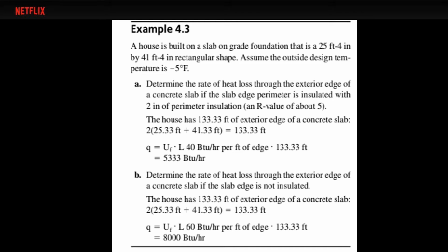So, next. Example 4.3, a house is built on a slab on grade foundation that is 25 feet 4 inches by 41 feet 4 inches in rectangular shape. Assume the outside design temperature is -5 Fahrenheit. Determine the rate of heat loss through the exterior edges of a concrete slab if the slab edge perimeter is insulated with 2 inches of perimeter insulation, an R value of about 5. The house has 133.33 feet of exterior edges of a concrete slab: 2 times 25.33 feet plus 41.33 feet is equal to 133.33 feet. Q is equal to U multiplied by L: 40 BTU per hour per foot of edge, multiplied by 133.33 feet, is equal to 5333 BTU per hour.